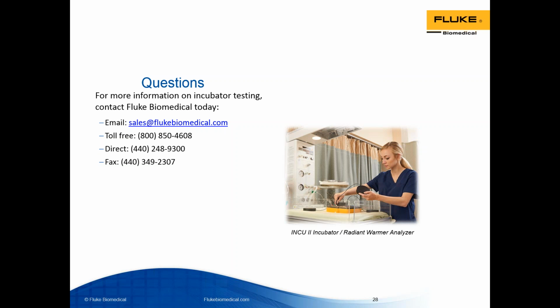So, the other part of it is using handheld test tools. Say, for example, I'm using a handheld test tool to measure the temperature. And if I need to measure the temperature at 5 different points of the mattress, yes, the temperature environment of the incubator may be disrupted, but on top of that, it also becomes more time consuming, right? And then again, having to do each parameter that way doesn't give you a full picture of what's happening together as the incubator is functioning.